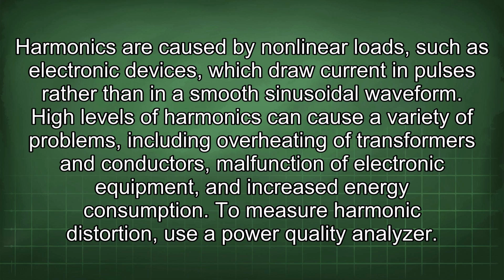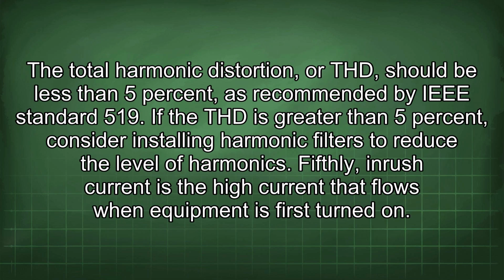To measure harmonic distortion, use a power quality analyzer. The total harmonic distortion, or THD, should be less than 5%, as recommended by IEEE Standard 519. If the THD is greater than 5%, consider installing harmonic filters to reduce the level of harmonics.